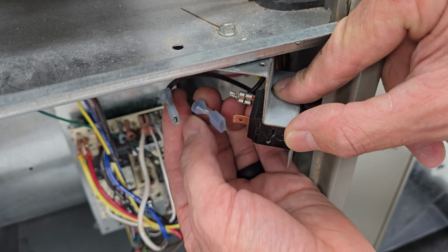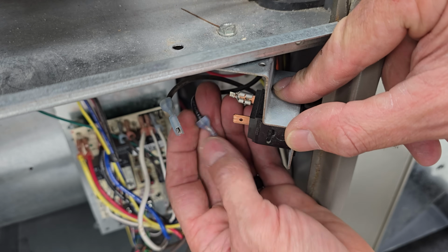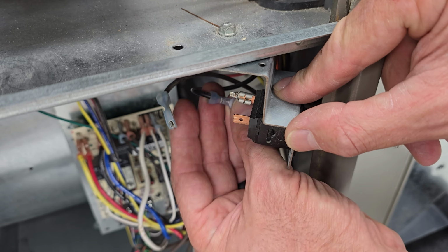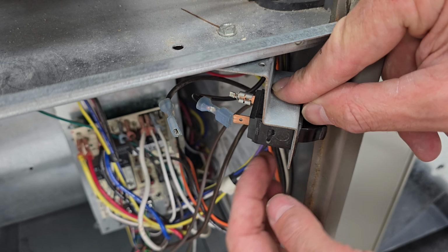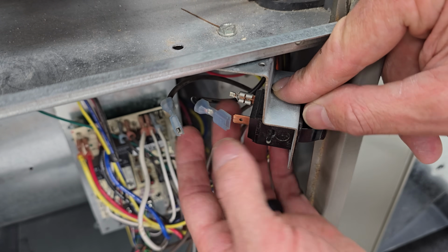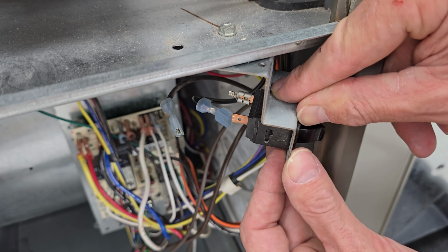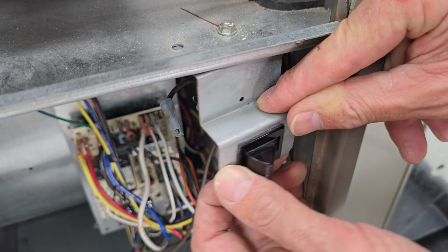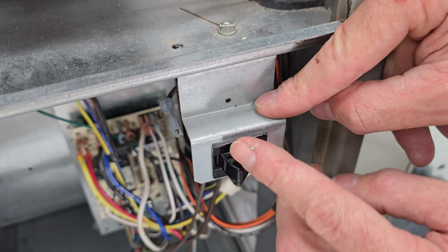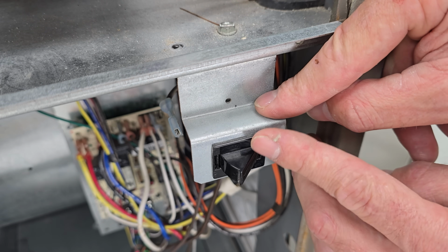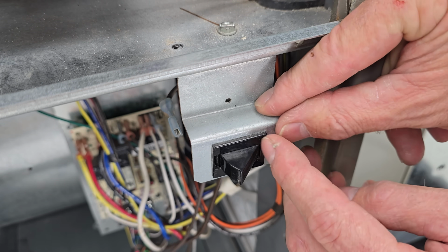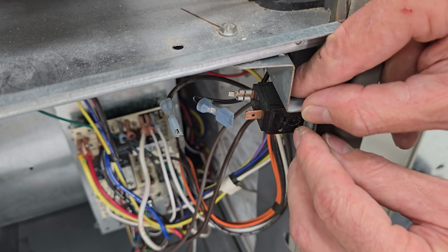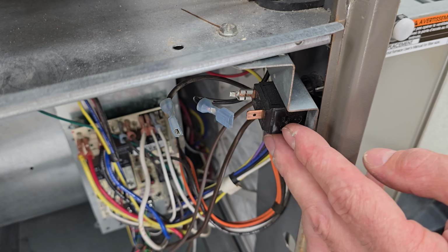And so you can see that that connector broke apart, so we would have to cut this off and put a new connector in its place. But just say that wasn't the issue, say this door switch was the issue, that could be a problem. I want to point out that this right here a lot of times ends up having burnt contacts inside and fails. And so you can also check this with electrical resistance right across here.